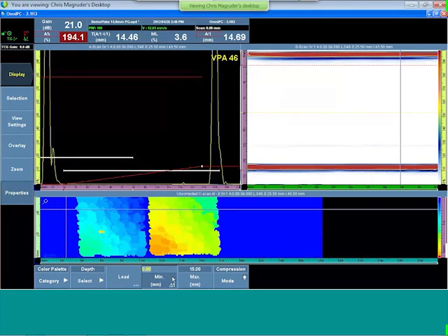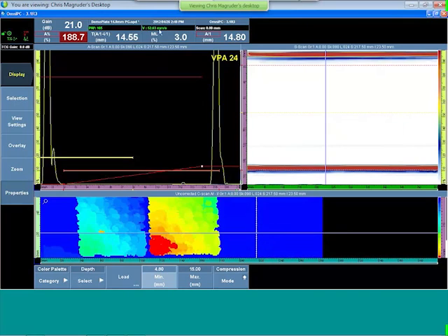So we go to the color palette, and I'm just going to slowly raise this 1 millimeter at a time, watching the color palette. So I can see low spots coming in here and here. And this color palette will determine where the red starts to appear in the data. So as I slowly limit the range of this, now I've found the low section, and we will measure that in another way shortly. But I want to find where the minimum red shows up, right here, making sure that some of this is still uncorroded at the nominal thickness, like we see this data point here. So between 4.8 millimeters and 15, I've got the low spots here.